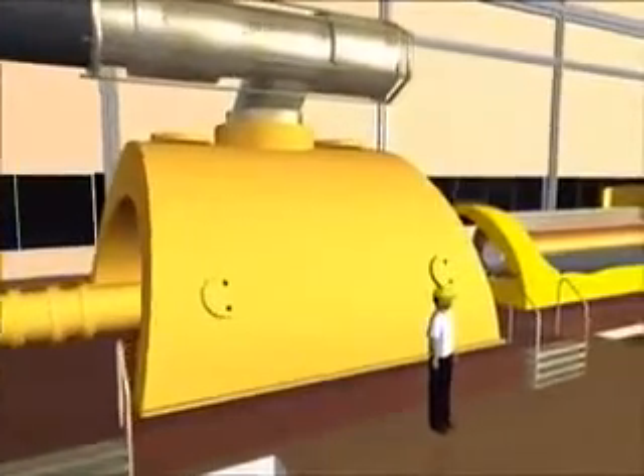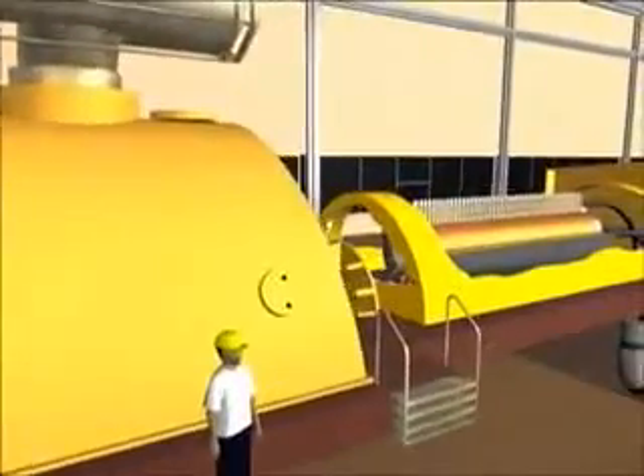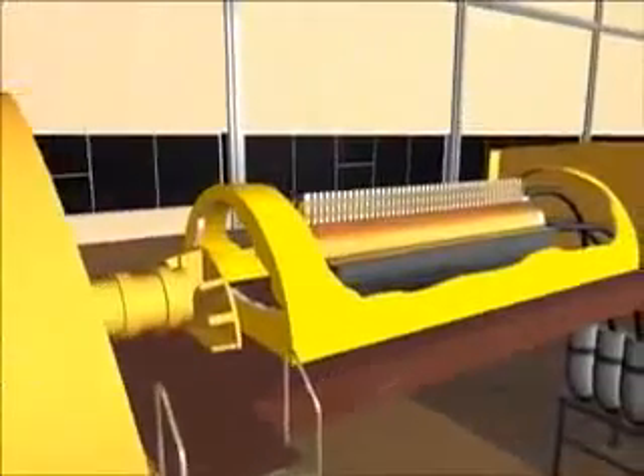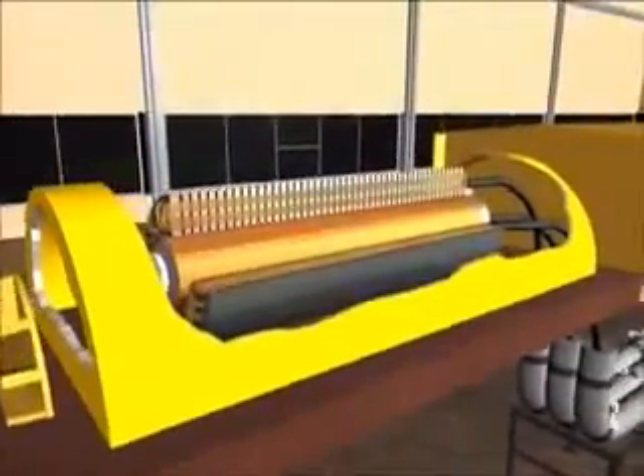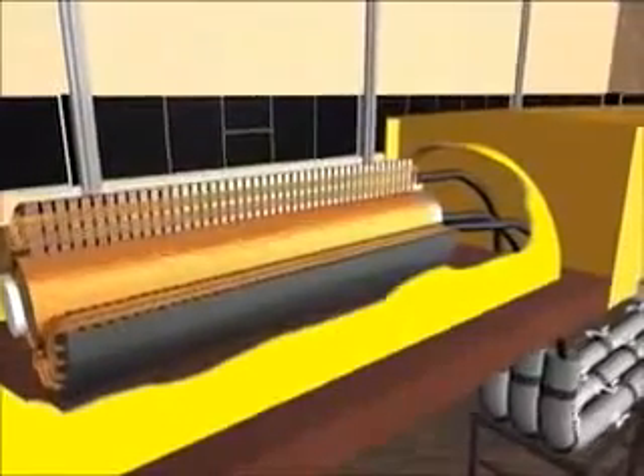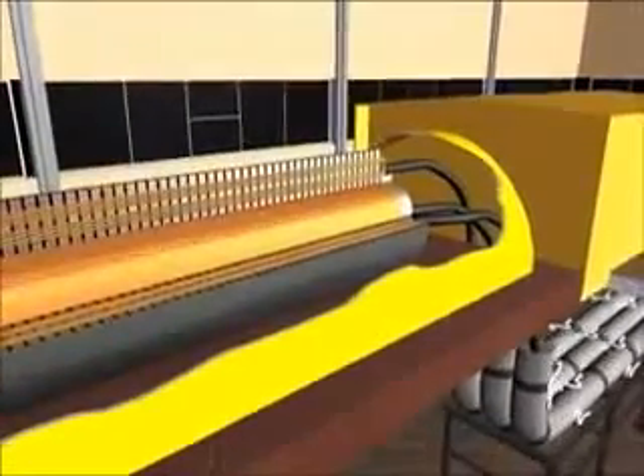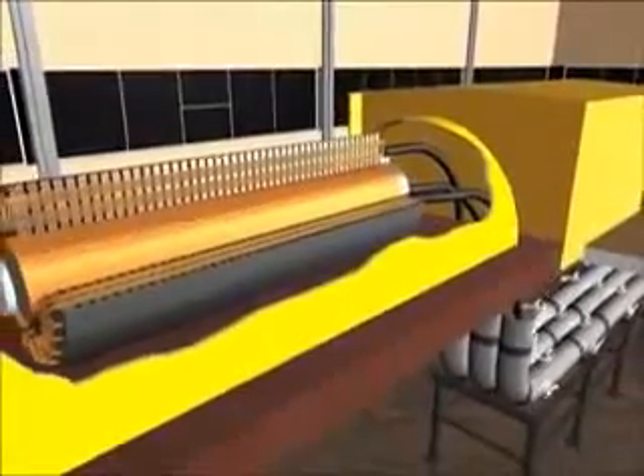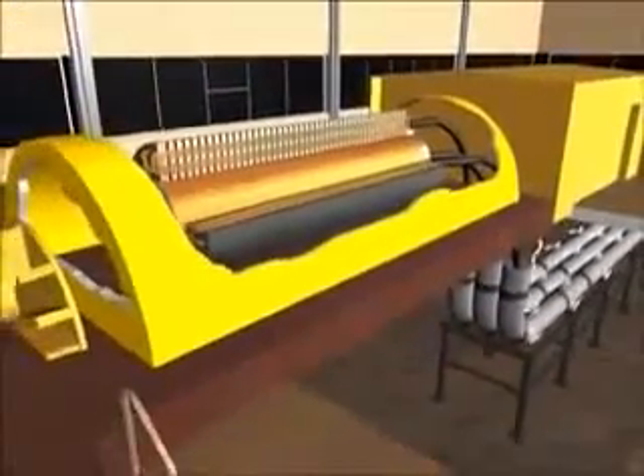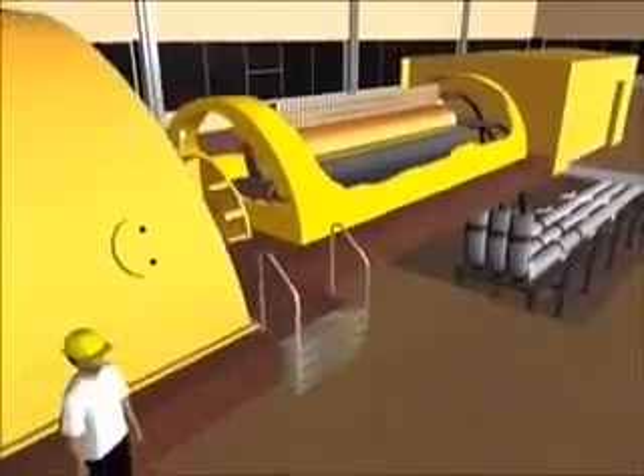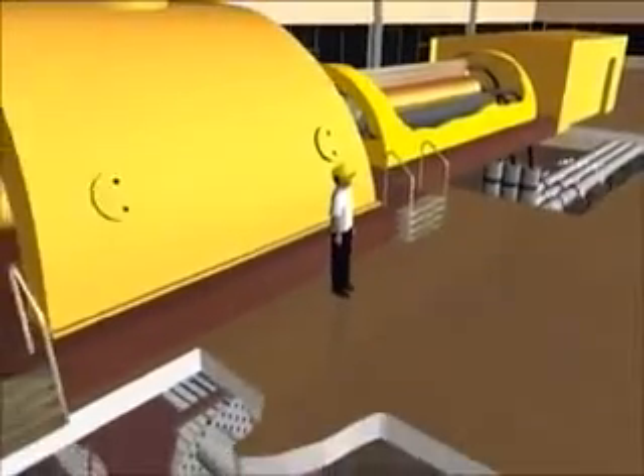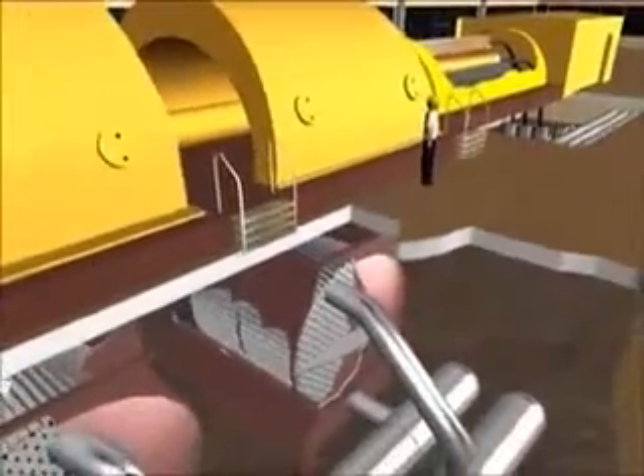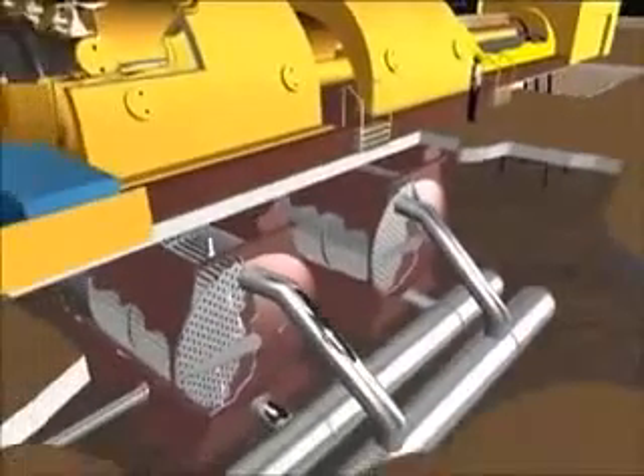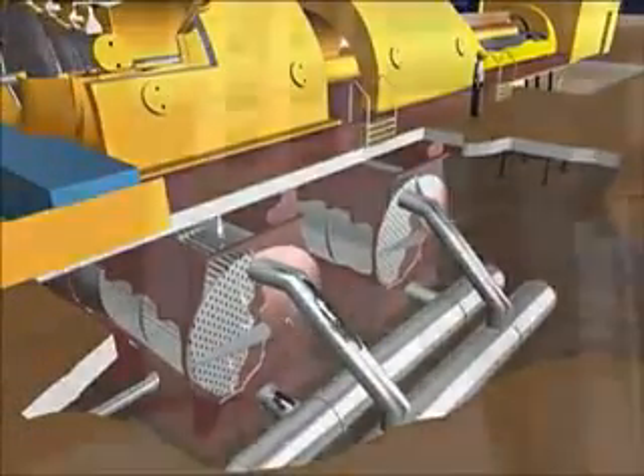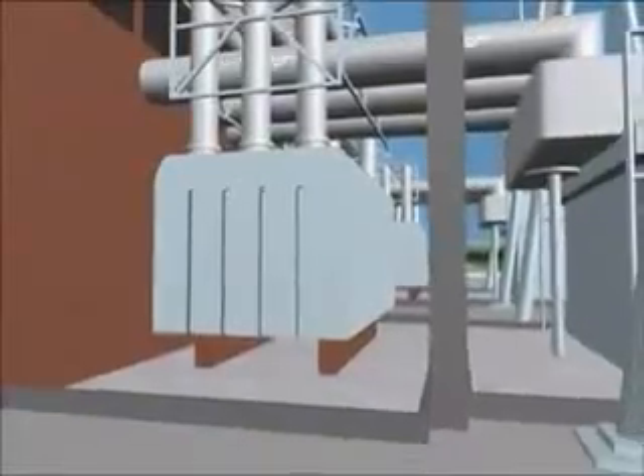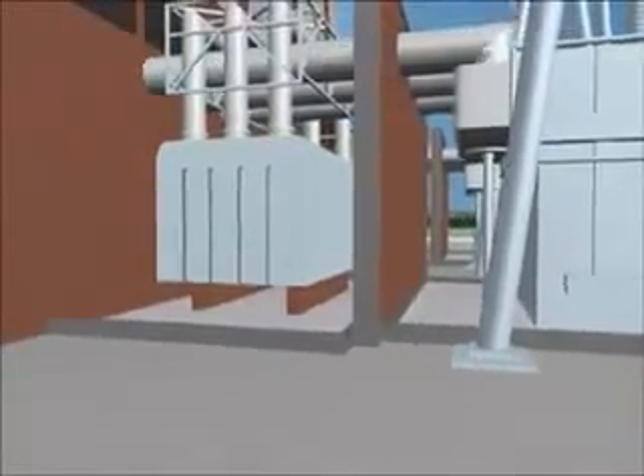The series of turbines spin at 3,600 revolutions per minute. This creates the power needed to spin the turbines and power the generator. The generator is the last section and creates the electrical charge. It creates 20,000 amps at 24,000 volts of electricity continuously. The silver tube below the turbine contains large copper bars, which carry the power to the generator step-up transformer outside the plant.